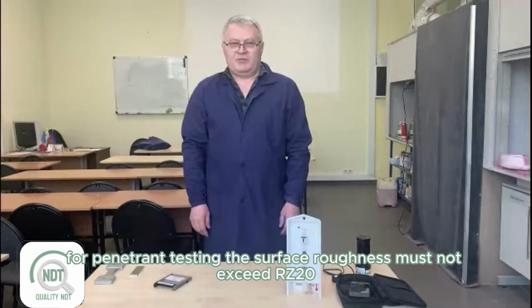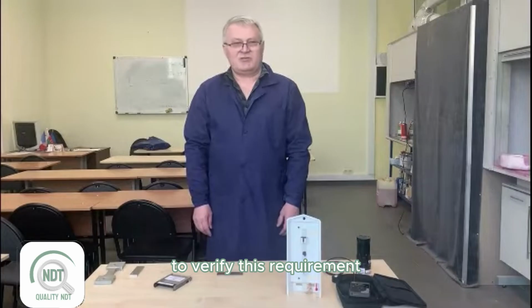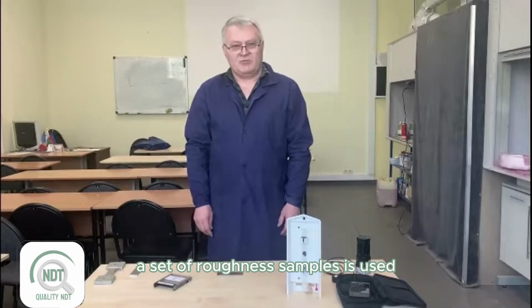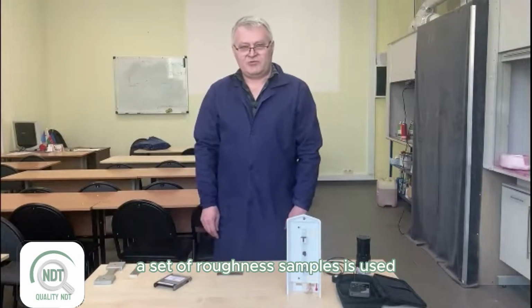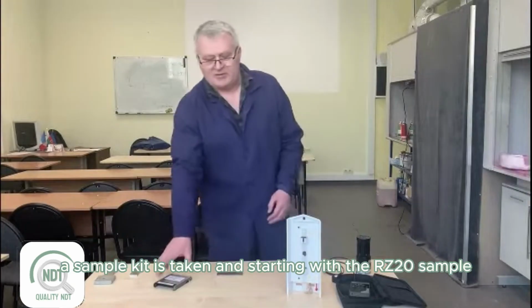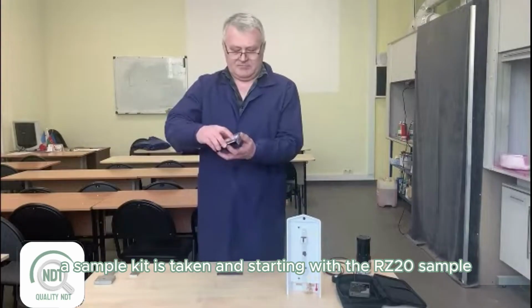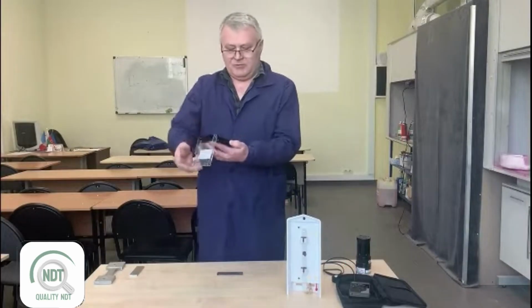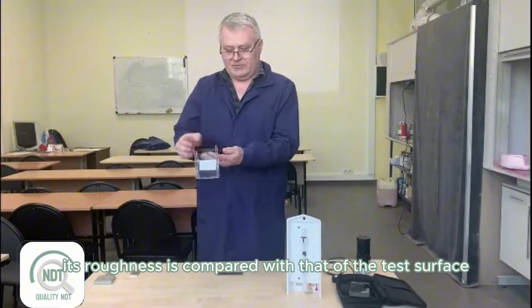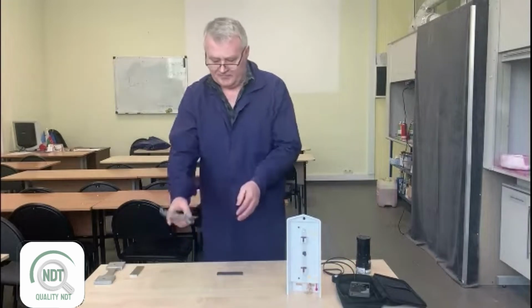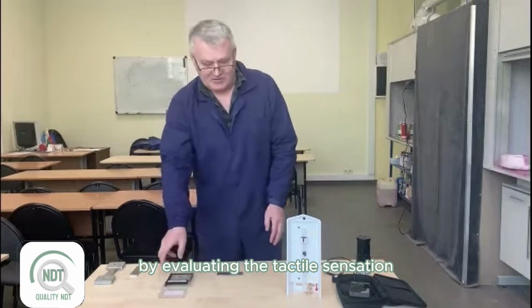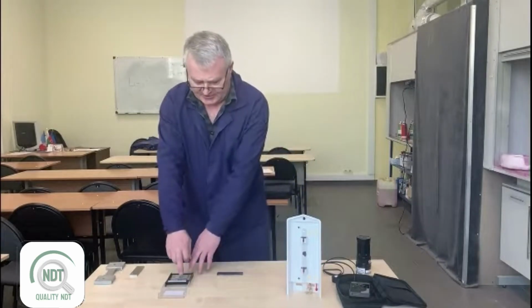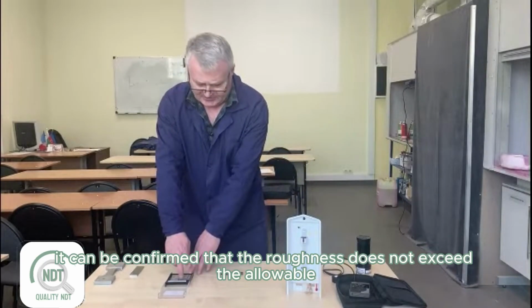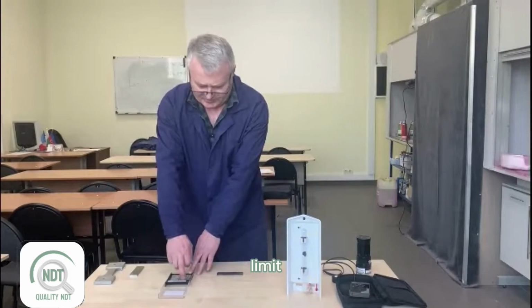For penetrant testing, the surface roughness must not exceed Rz20. To verify this requirement, a set of roughness samples is used. A sample kit is taken, and starting with the Rz20 sample, its roughness is compared with that of the test surface. By evaluating the tactile sensation in each case, it can be confirmed that the roughness does not exceed the allowable limit.